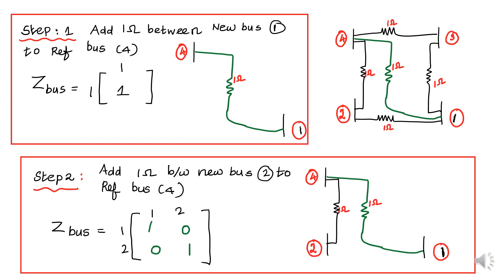What is step number 1? Add 1 ohm between new bus 1 and reference bus 4. I have to redraw the diagram here. The Z-bus matrix has 1 element — put Z(1,1) equal to 1. The impedance here is 1. The Z-bus consists of only 1 element. That is step number 1.